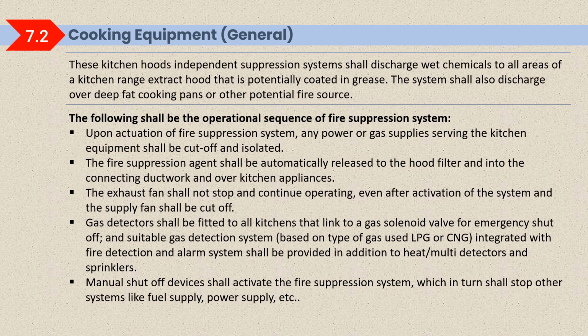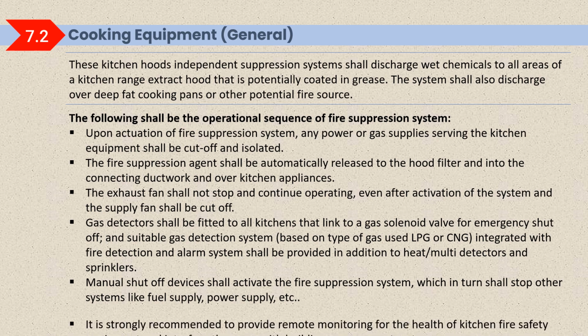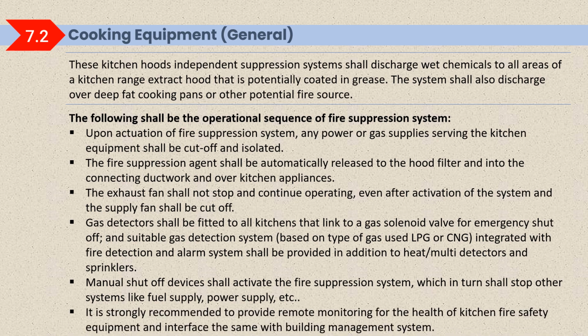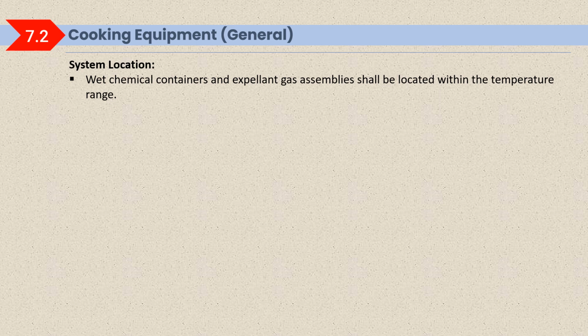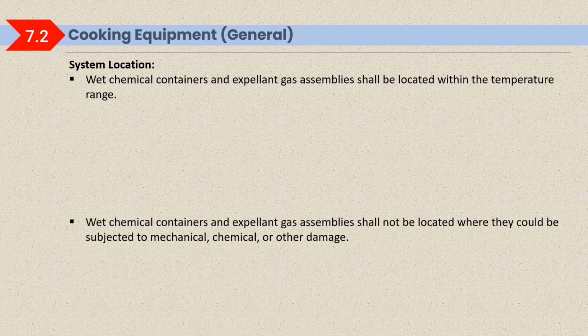A manual shut-off device shall activate the fire suppression system, which in turn shall stop other systems like fuel supply, power supply, etc. It is strongly recommended to provide remote monitoring for the health of kitchen fire safety equipment and interface the same with the building management system to monitor the health of the kitchen equipment. It can be connected with the building management system, BMS. System location. Wet chemical containers and expellant gas assembly shall be located within the temperature range.